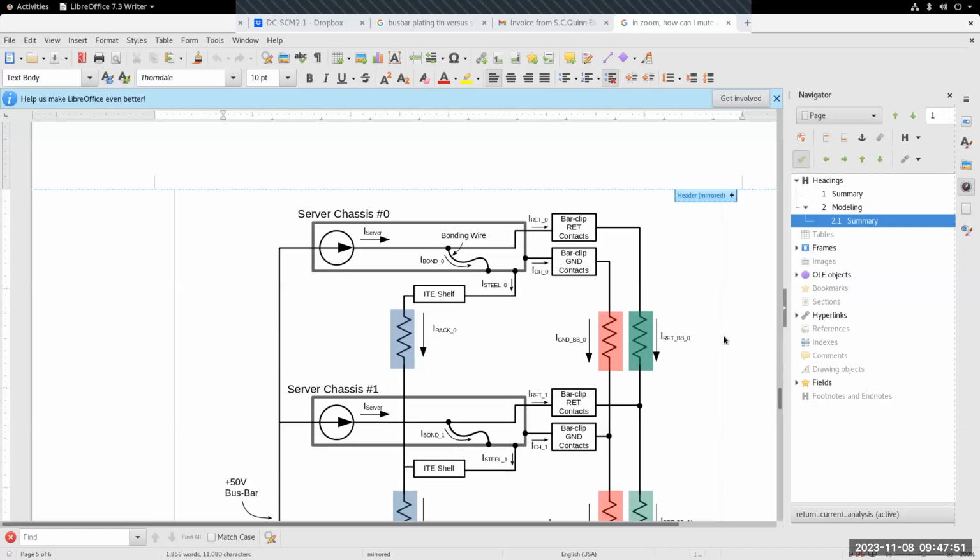It's pretty difficult to instrument our systems without introducing additional impedances. So we've got compute and switch trays. I kind of instrument a tray, but I have to remove the tray on top of it to fit the probes. So we're close.